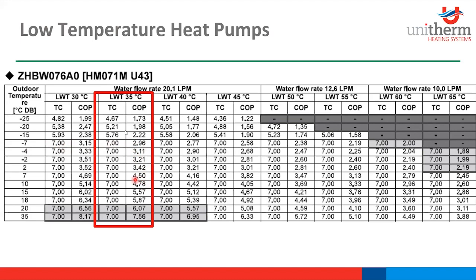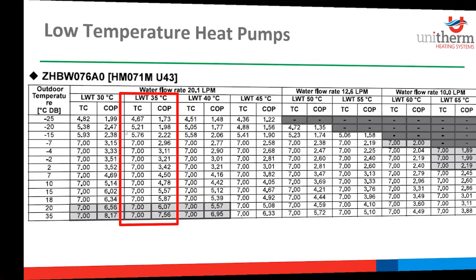Average weather in Ireland is 10 degrees on average, supposedly all year round, but obviously we will get the minuses at winter time. So even at 10 degrees on average, if you take an average of 4.78, the seasonal COP for this unit for the 5, 7 and 9 kilowatt is 4.45. So even all the way up to 60 degrees leaving water temperature, you're still getting 100% performance. So you're still getting the 7 kilowatts out of it.